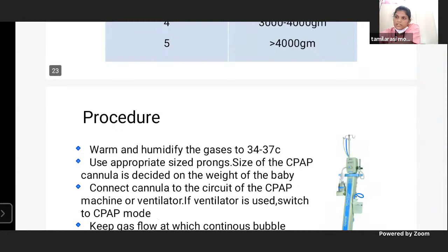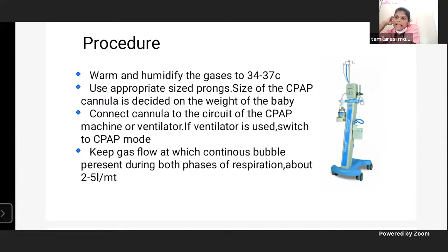Next, we will see the procedure of this CPAP. First, if we are going to use CPAP, we should check the temperature, that is, the humidity and temperature. The warmth and humidity of the gases should be 34 to 37 degrees Celsius. Use the appropriate size prong; the size of the CPAP cannula is decided on the weight of the baby. Connect the cannula to the circuit and then to the machine or ventilator. If a ventilator is used, we switch on the CPAP mode and keep the gas flow at which a continuous bubble is present.